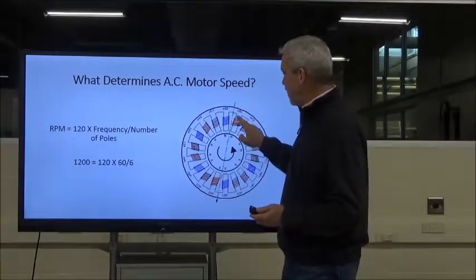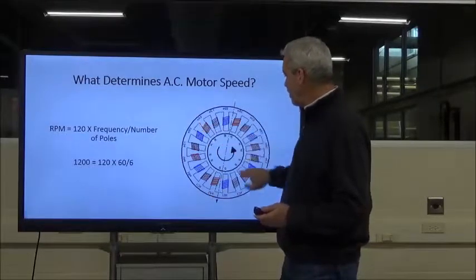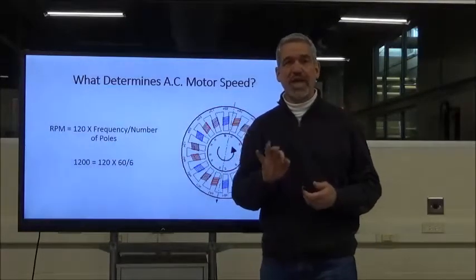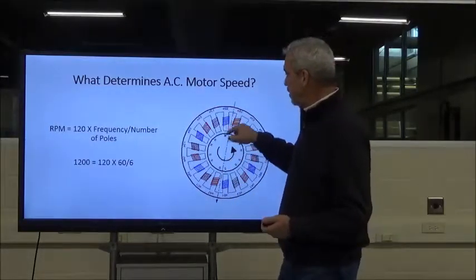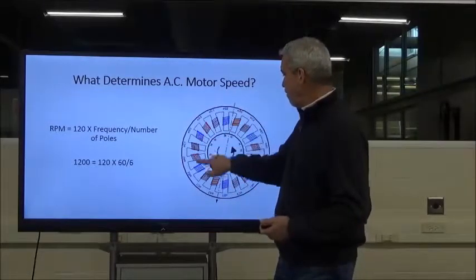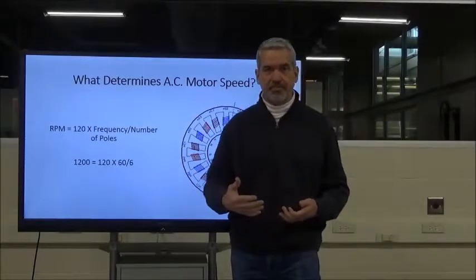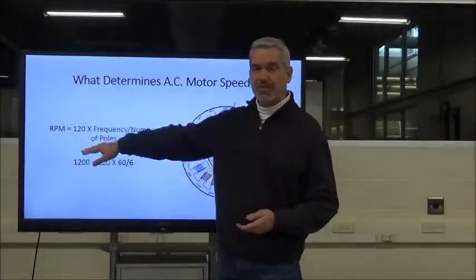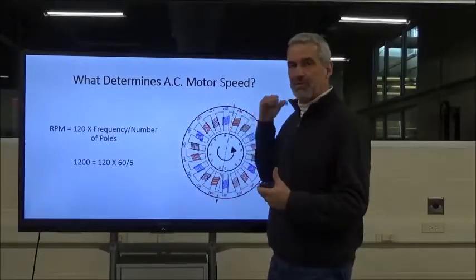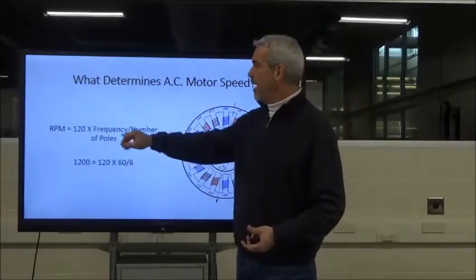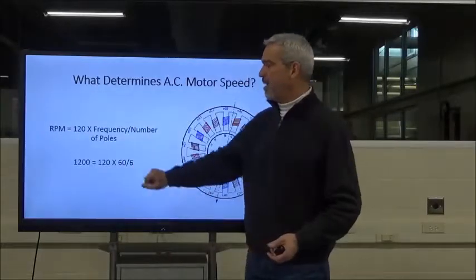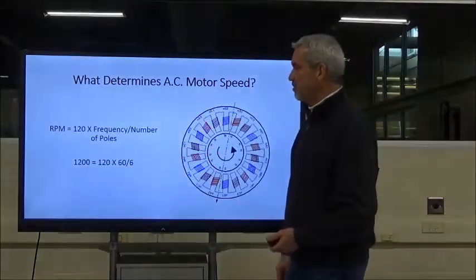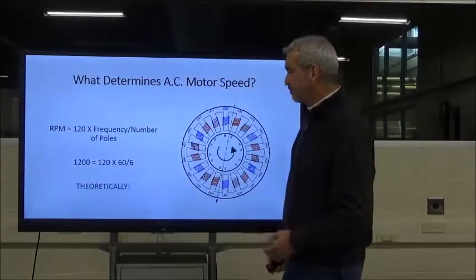This is a six-pole motor — there are six poles per phase. Using the formula: 120 × 60 ÷ 6 = 1,200 RPM theoretically. Each time we add more poles, we slow the motor further. That's the relationship between pole count and speed.